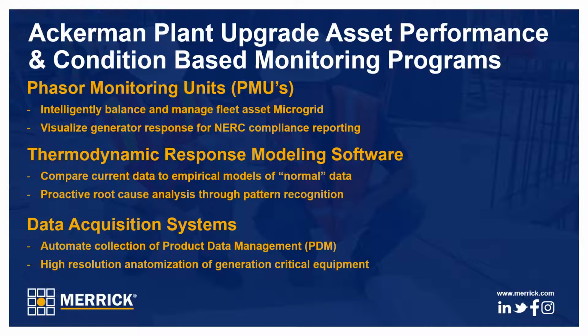In addition to this project, Merrick has performed other asset performance and condition-based program projects at multiple coal, gas, and hydro power plant facilities. At Ackerman specifically, Merrick led the owner engineering efforts for 2 other projects. The first was the addition of a thermodynamic response modeling software. This project encompasses monitoring of system feedback signals to support the creation of an empirical model and monitor the cycle. It also provided a proactive root cause analysis. For example, cooling water flow, heat recovery steam generator differential pressure, and systems drains are key inputs into the model.